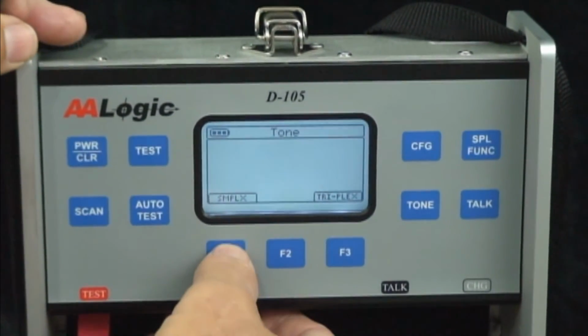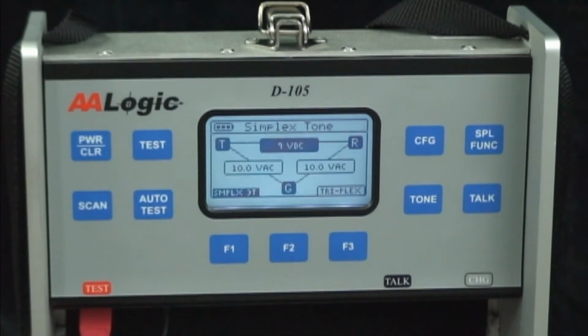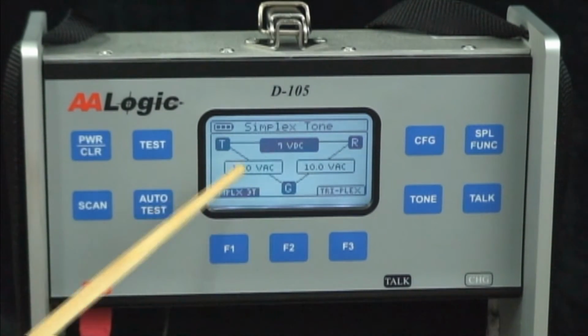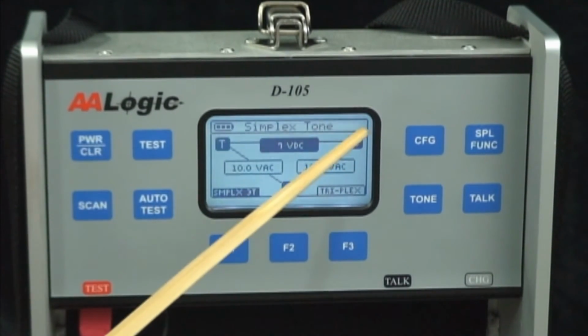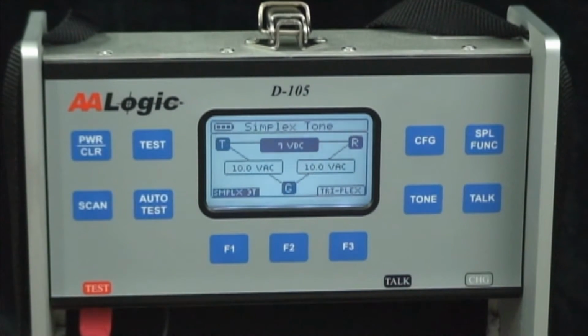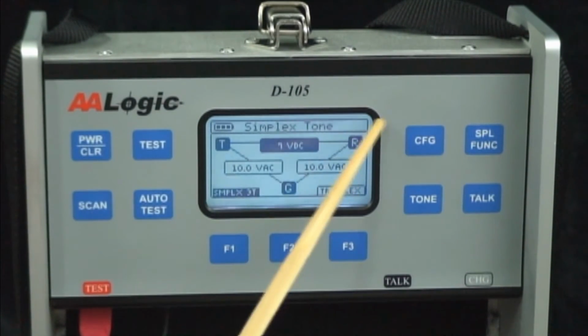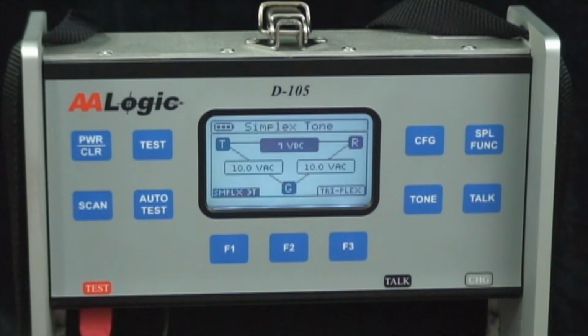Pressing Simplex will show us the display and it indicates that we have 10 volts AC on the tip to ground and 10 volts AC on the ring to ground. Between the tip and the ring, we're currently seeing 9 volts. This is very convenient because the user can also see voltage on the pair at the same time that tone is being transmitted.